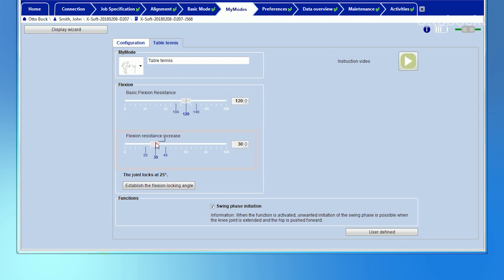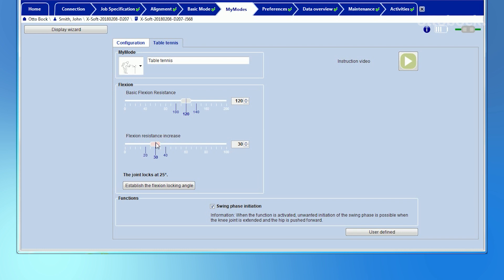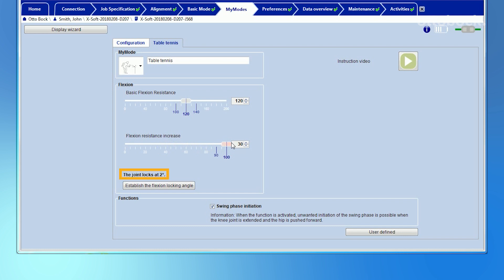The second parameter is named flexion resistance increase. A higher value will increase the level of flexion resistance quickly as the knee flexes, and a lower flexion angle will be achieved, and vice versa.